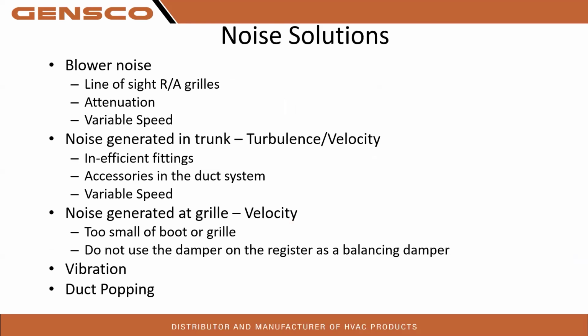Yeah, noise solutions, line of sight, return air grills, attenuation. You've heard that before, haven't you? Noise generated in trunk turbulence, velocity. Sometimes the dampers will rattle, so I recommend definitely tightening those all the time. Noise generated at the grill. Here you go again.